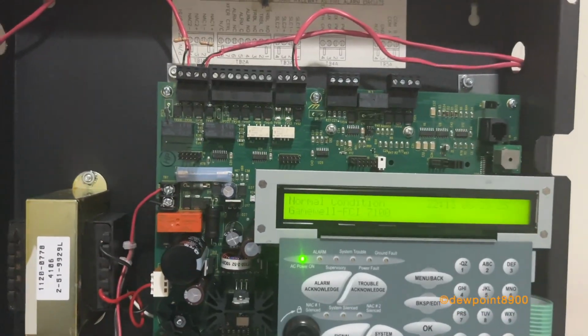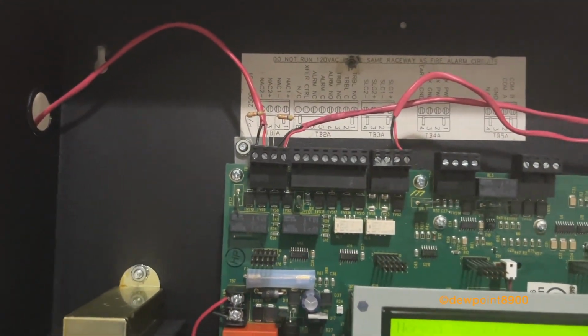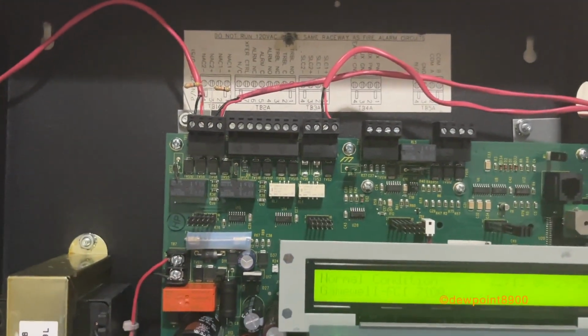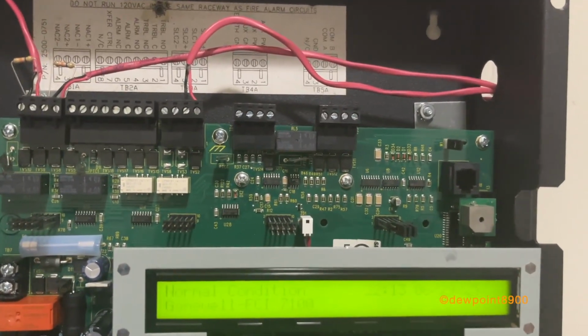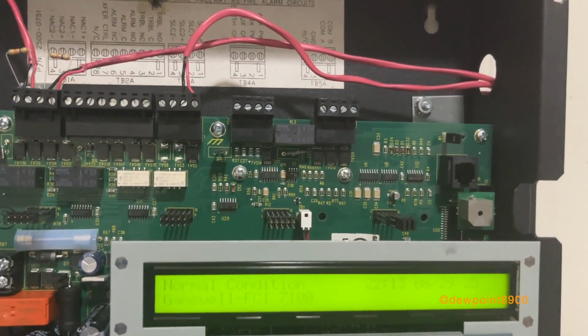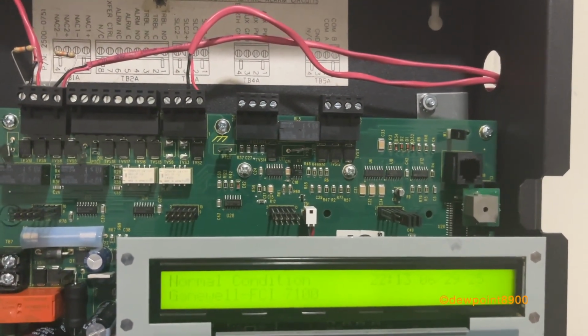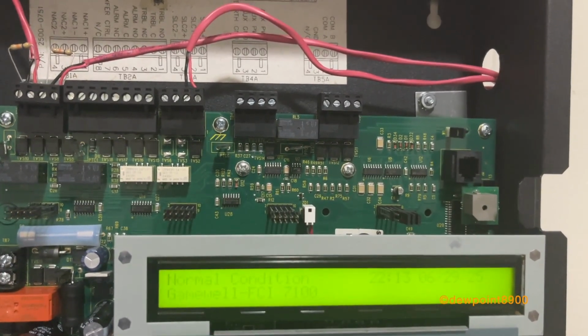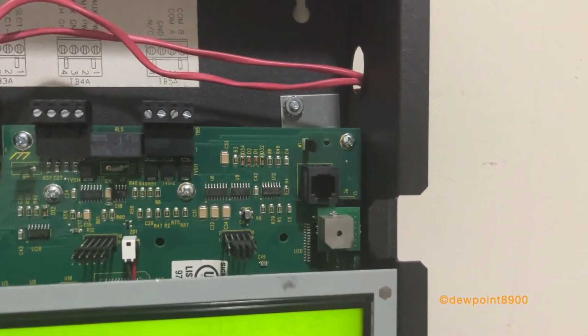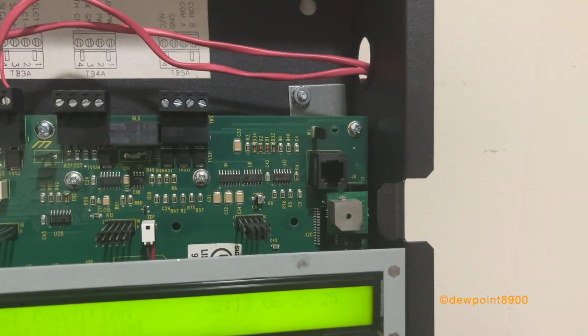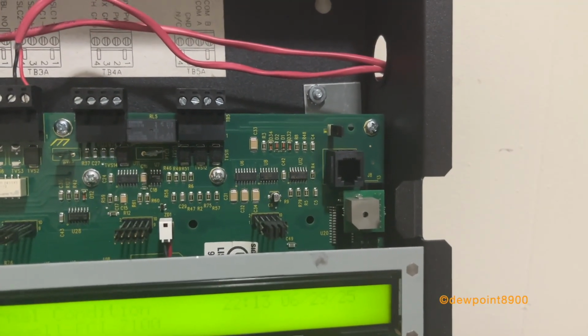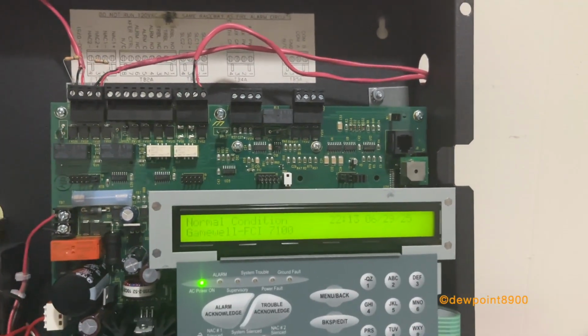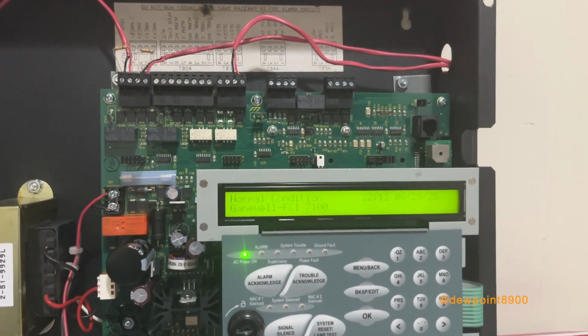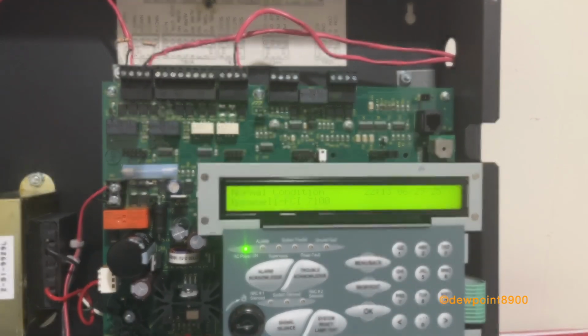There was a CAOM module, which converted the signal circuits or SLC loops to Class A circuits. There was an MCOM module, which provided one additional output, either a city box, reverse polarity, or a releasing solenoid. There was a PTRM module, which provided isolation and transient protection for a printer interface. Finally, there was an INI module, which could connect up to 64 7100 panels together in a network.